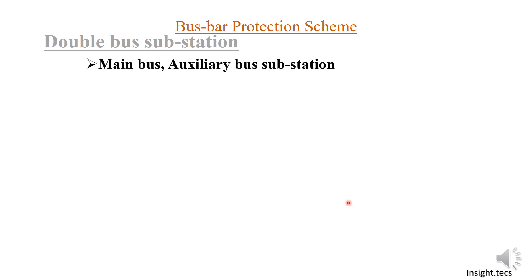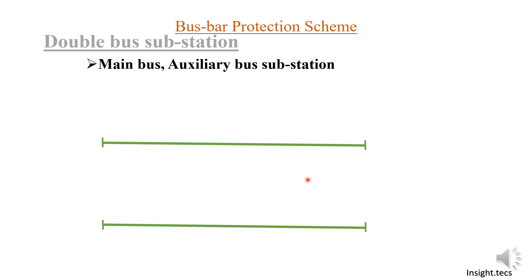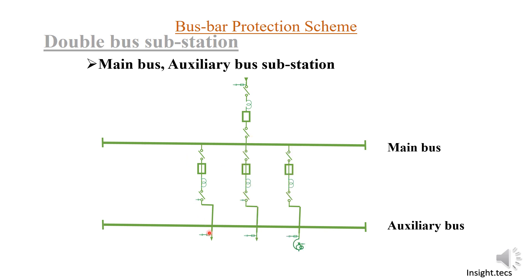In today's video we will learn in more detail about the main bus and auxiliary bus substation. This is the main bus and this is the auxiliary bus. It has an incoming feeder and a transformer as the outgoing feeder. This scheme also has a bus coupler arrangement similar to the two bus system. The auxiliary bus has a selection isolator that selects whether power is to be transferred through the main bus or through the auxiliary bus, with one extra isolator provided for this selection.